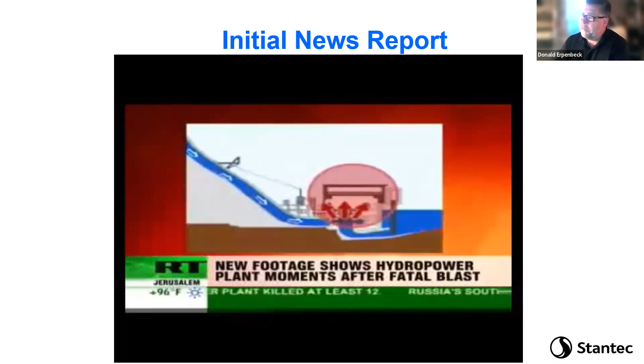So upon the failure, when the water's shooting out of the top, all units went offline in 49 seconds. So between 8:13 and 8:14, all the units tripped off. All the water flying through basically shorted out all the electrical equipment, flooded the whole lower elevations. Because of how quick it all happened, they were actually unable to close off flow to most of the turbines when the electrical systems were all shorted out in the transformers and substations.